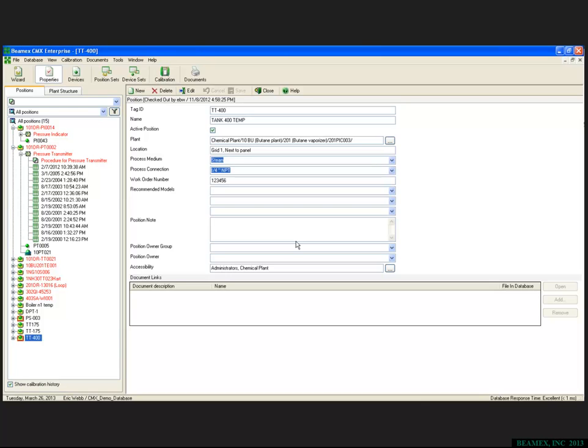So what we're looking at right now is the Beamex CMX calibration management software. And I'll just give you a brief tutorial here on what we're looking at and what the relevance of the information is. If you look on the left side where my pointer is here, this basically gives a listing of all of the assets that you would have in your database. Now, we have two different ways of looking at that. We can look at this by position, meaning we can look at it by, for example, the tag ID, which is what we're looking at right now. The very bottom one is highlighted in blue, which is a TT400.